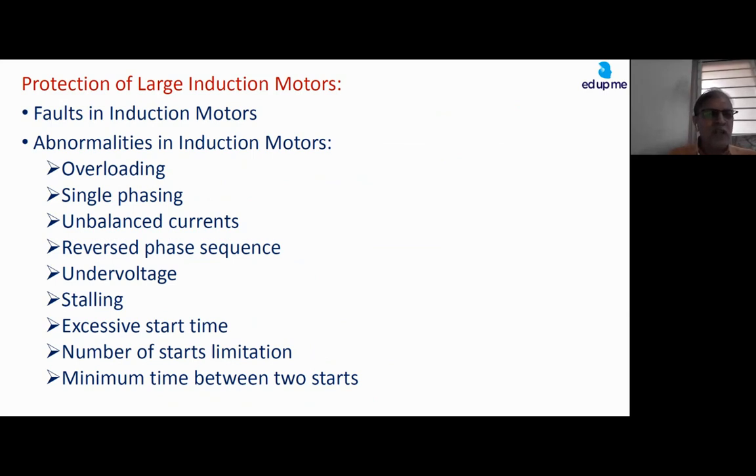I hope you can understand. You are in the lift on the fourth floor and you are pushing the button for the seventh floor, and the lift takes you to the ground floor rather than the seventh floor. Your process will get reversed. The boiler feed pump is pumping water from the deaerator to the boiler drum. Instead, it will take water from the boiler drum and feed it to the deaerator. Reverse process. That is the problem.